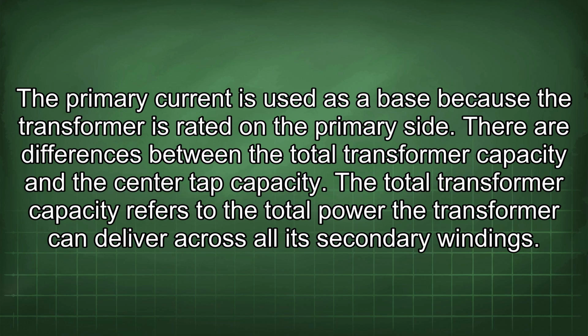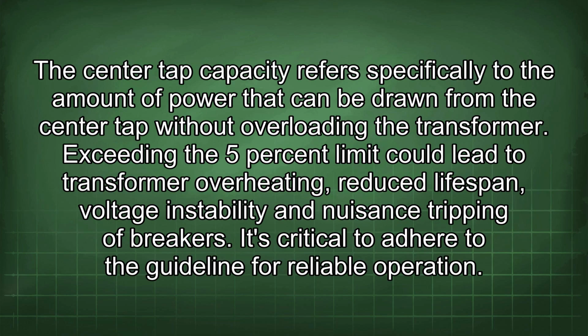There are differences between the total transformer capacity and the center tap capacity. The total transformer capacity refers to the total power the transformer can deliver across all its secondary windings. The center tap capacity refers specifically to the amount of power that can be drawn from the center tap without overloading the transformer. Exceeding the 5% limit could lead to transformer overheating, reduced lifespan, voltage instability, and nuisance tripping of breakers. It's critical to adhere to the guideline for reliable operation.